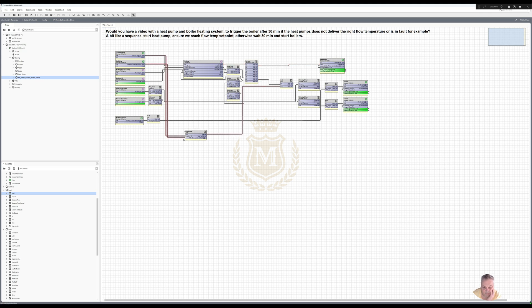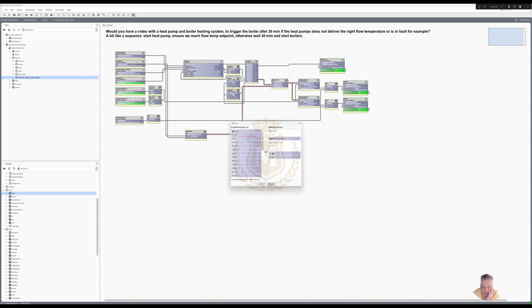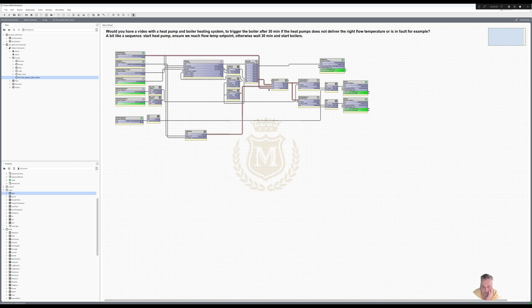So now we've got the enable and the gas safety tied into just the boilers — boilers control. I think what we'll do as well is add a heating enable into that just as a secondary precaution. We've done that — it's never going to get to a true value anyway because that will be off with the heating, but it's just belt and braces, adding that extra bit. So we've got the sequencer, the fault, and it also has to be enabled before the boilers will come on.